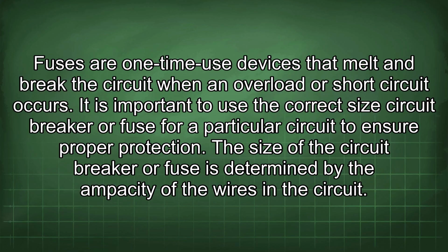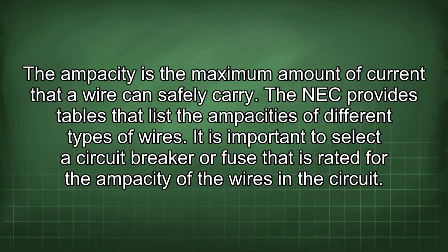It is important to use the correct size circuit breaker or fuse for a particular circuit to ensure proper protection. The size of the circuit breaker or fuse is determined by the ampacity of the wires in the circuit. The ampacity is the maximum amount of current that a wire can safely carry. The NEC provides tables that list the ampacities of different types of wires. It is important to select a circuit breaker or fuse that is rated for the ampacity of the wires in the circuit.